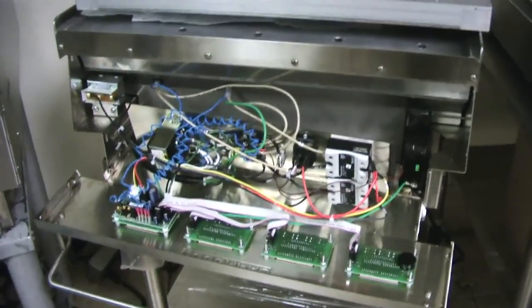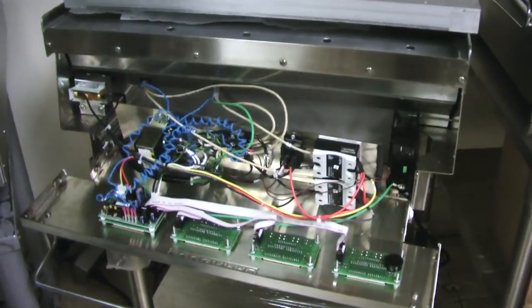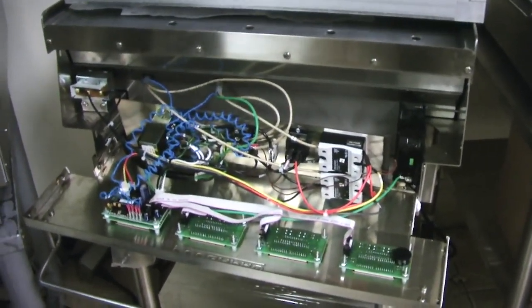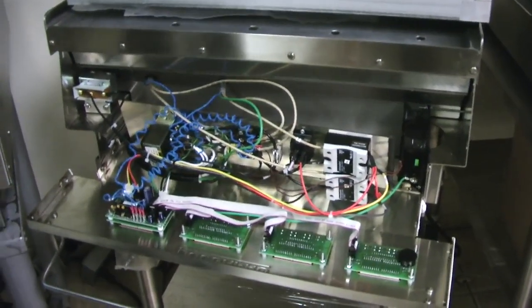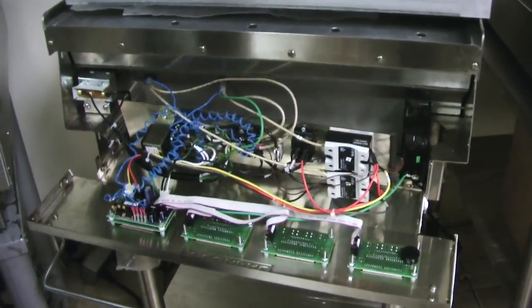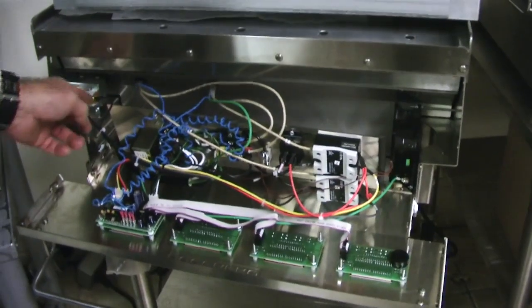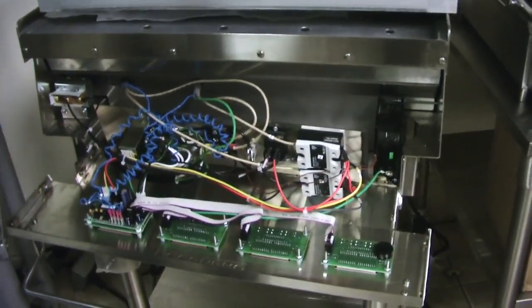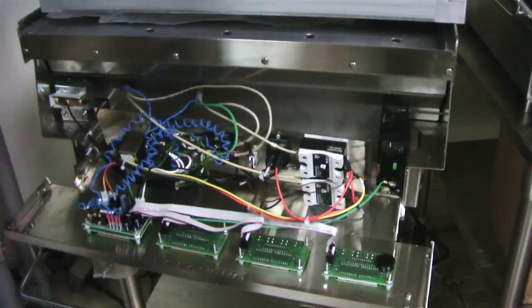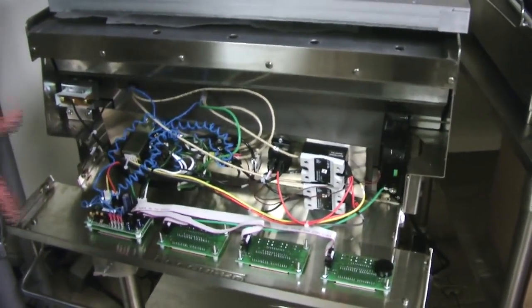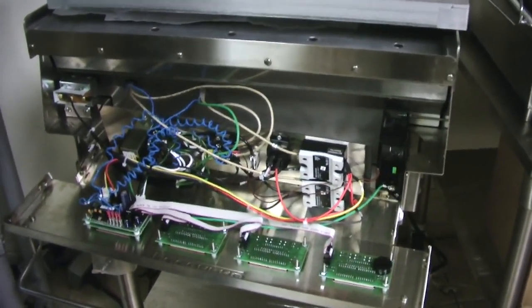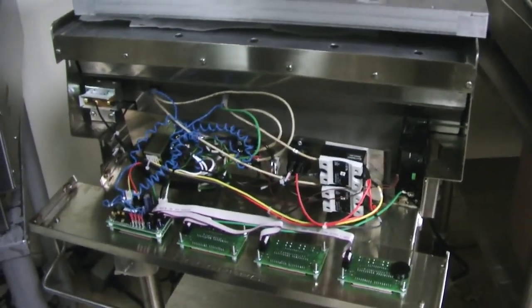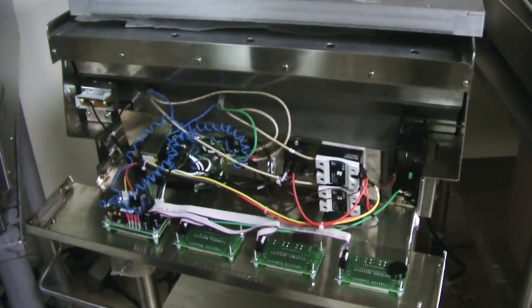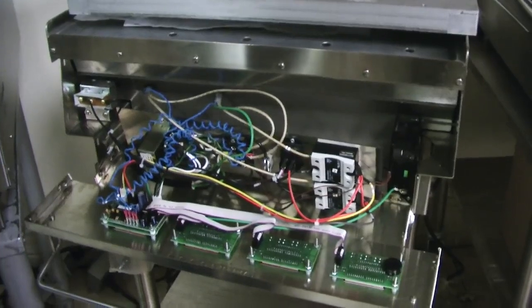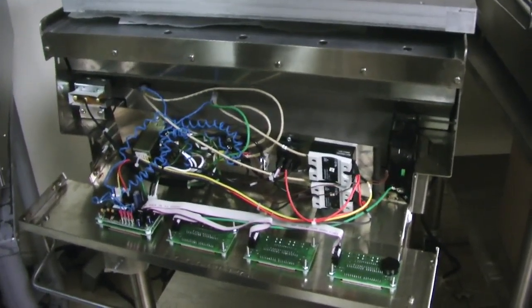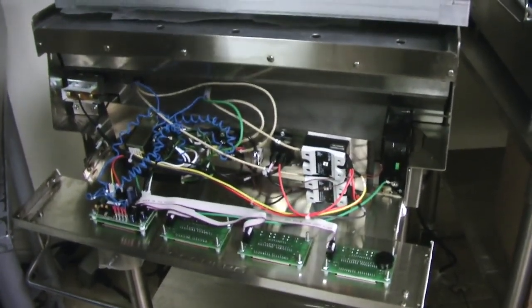That concludes the troubleshooting. Of course, the high temp limiter is set to 550. One way to check the high temp limiter, obviously you guys know, is just to join two of these together and bypass the limiter. If that functions, that tells you there's something wrong with the high temp limiter. We've had one go out in about 100 pieces of equipment. I don't think this is a very reliable, expensive piece of component here. I don't think that is going to be the problem, but you never know. It did happen once. It happened again.